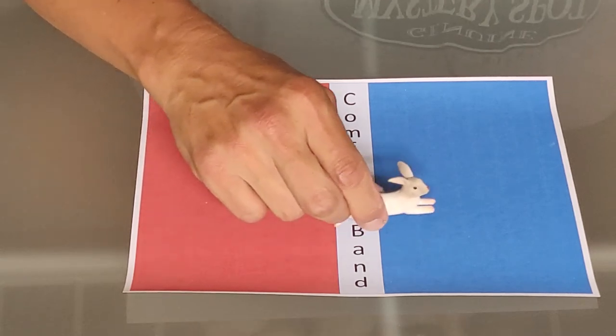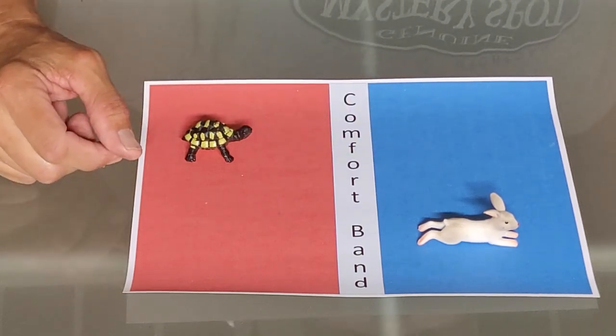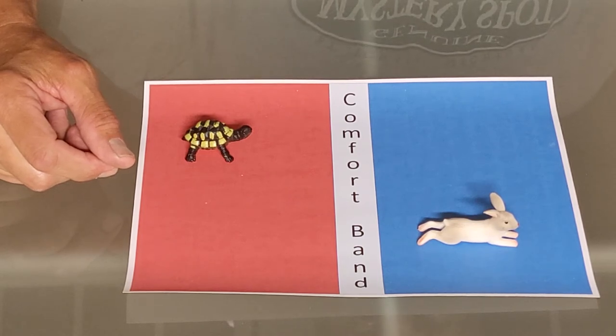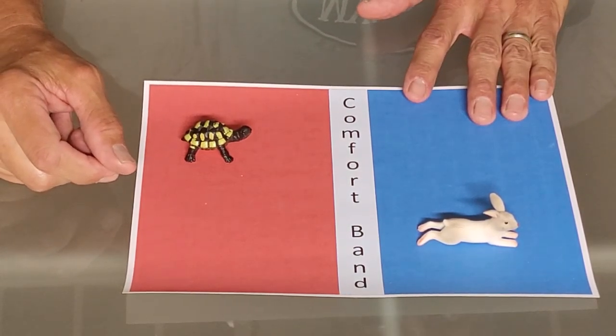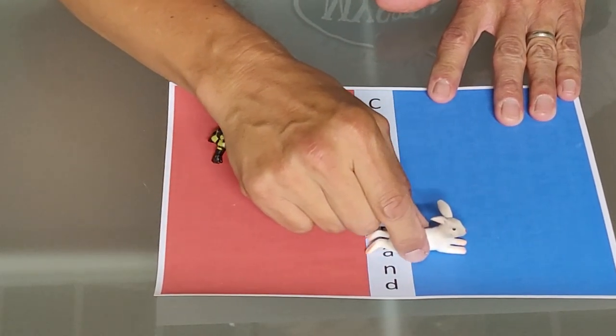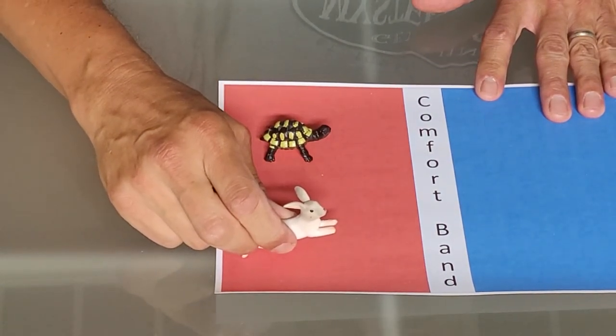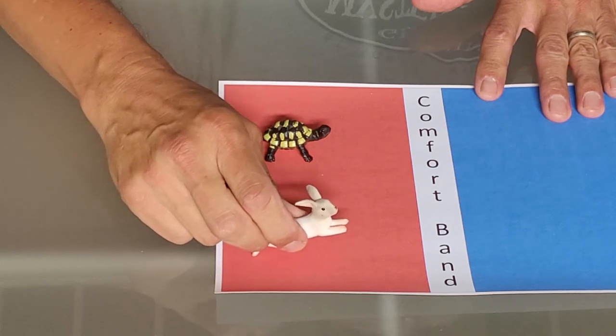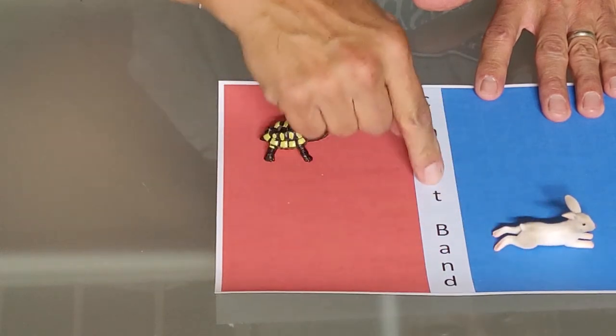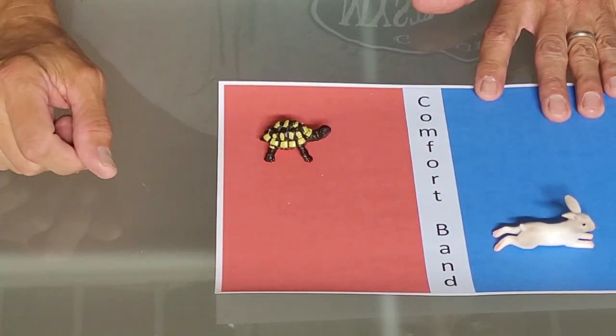He's not very efficient but he gets there in a hurry, and he actually exceeds your 75 degrees — maybe comes down to 72 or 71 degrees. He sits there, thinks the race is over, doesn't do anything, turns off. The problem is the race is far from over, because heat from your house and outside comes back, and every 20 minutes he has the same jackrabbit start, doing wear and tear on his motors and decreasing the life of the unit. Meanwhile you're always vacillating between it being too cold and too hot.